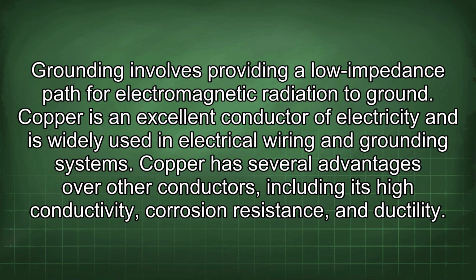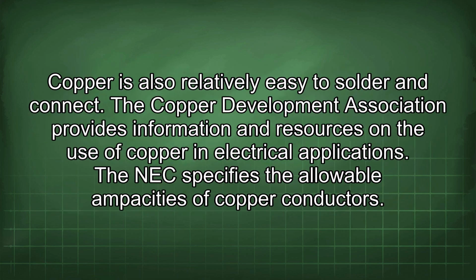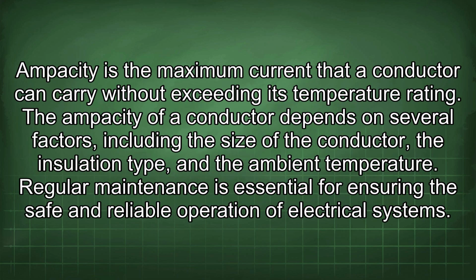Copper is an excellent conductor of electricity and is widely used in electrical wiring and grounding systems. Copper has several advantages over other conductors, including its high conductivity, corrosion resistance, and ductility. Copper is also relatively easy to solder and connect. The Copper Development Association provides information and resources on the use of copper in electrical applications. The NEC specifies the allowable ampacities of copper conductors. Ampacity is the maximum current that a conductor can carry without exceeding its temperature rating. The ampacity of a conductor depends on several factors, including the size of the conductor, the insulation type, and the ambient temperature.